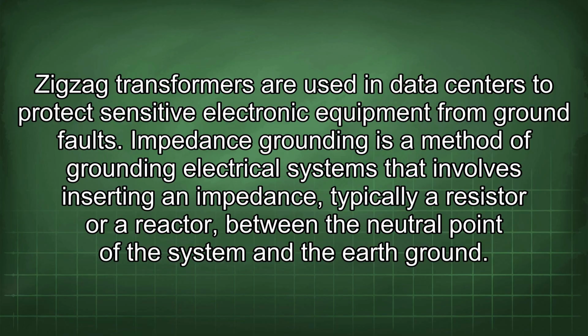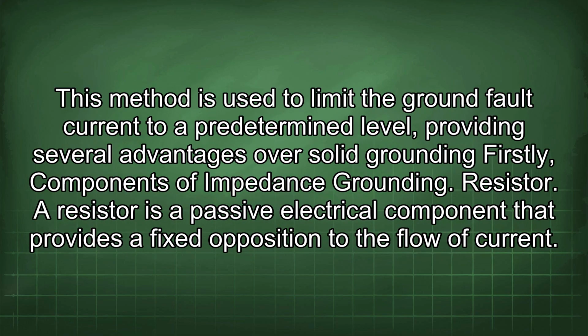Impedance grounding is a method of grounding electrical systems that involves inserting an impedance, typically a resistor or a reactor, between the neutral point of the system and the earth ground. This method is used to limit the ground fault current to a predetermined level, providing several advantages over solid grounding.